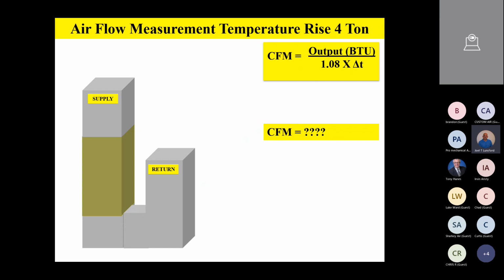And that gives us a CFM of what? So 41,221 on your calculator divided by 21.6 should give us a CFM on the second temperature rise method of 1908. So on a 4-ton unit, I'm measuring a particular speed tap, and I see that I've got a little over 1900 CFM on a 4-ton unit.